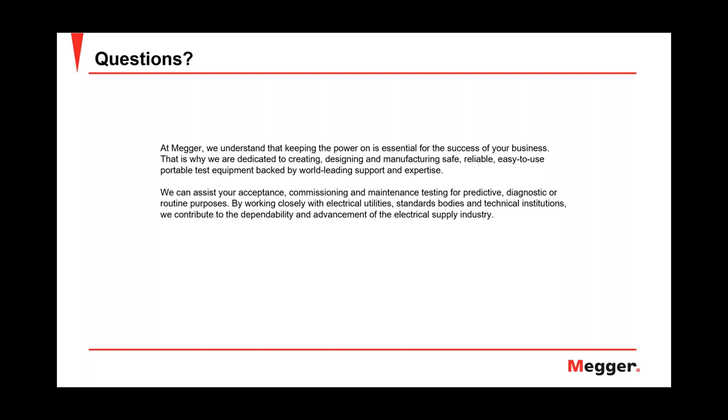Thanks, Joseph. Our next question is over to Jason. Jason, can TDRs work if the neutral is corroded? Okay, so for this question, we have to understand, as Glenn mentioned, you need two parallel conductors to be able to do a TDR trace.